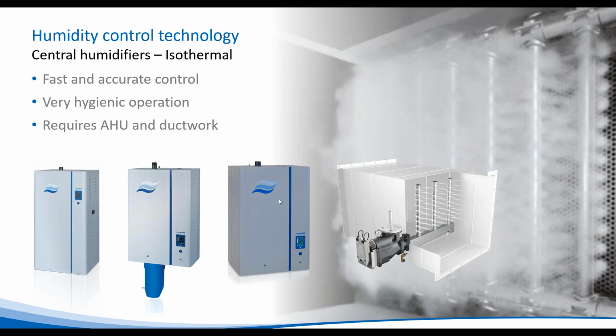There is a gas-fired unit if we're using gas, but with decarbonisation we see less and less of those now. Or in this picture here, you can see a live steam humidifier where a pressurized steam supply is available. It can be utilized. Here it's going through a valve to meter the steam into the air handling unit or the duct, and then there's a steam distribution system inside the duct that's releasing steam into the air to increase relative humidity. The background picture you can see here is inside a duct, and this is a short absorption distance manifold that's used to inject steam across the whole cross section of the air handling unit, because this controls the absorption distance.